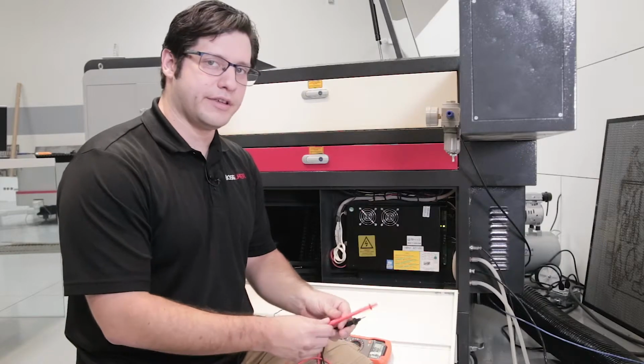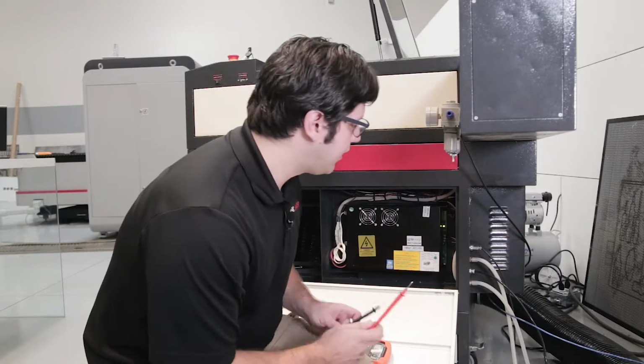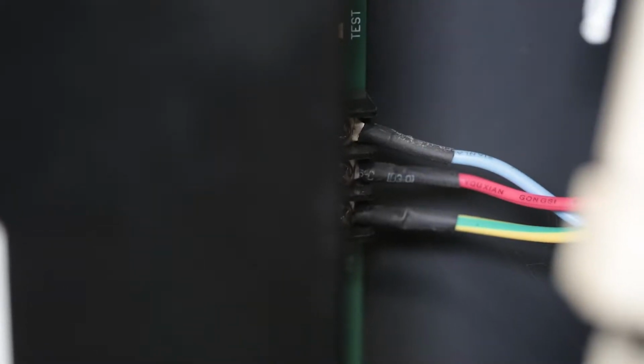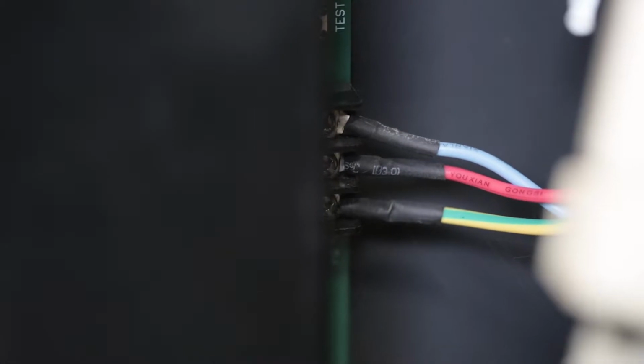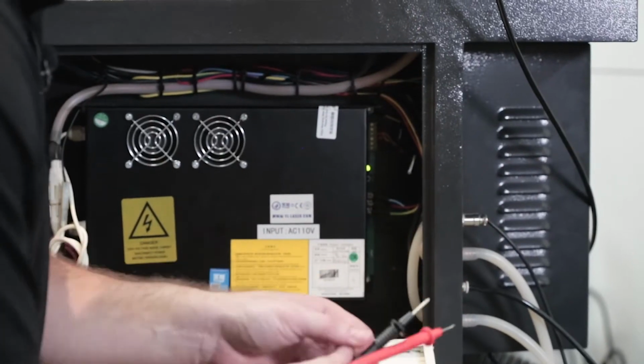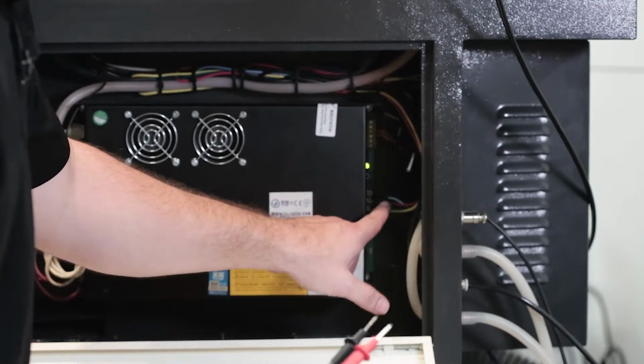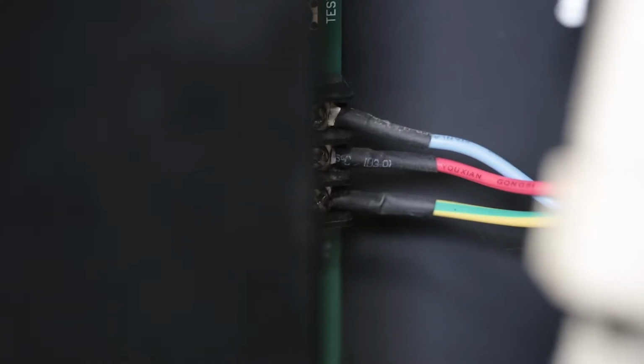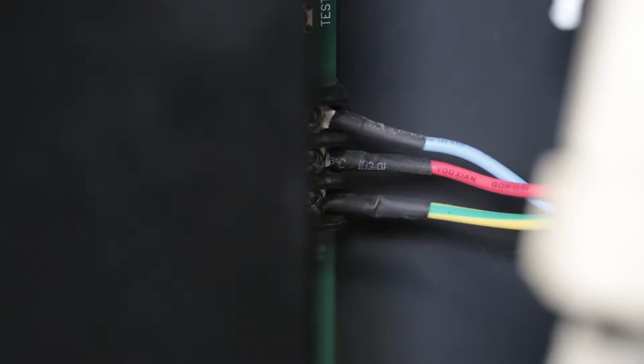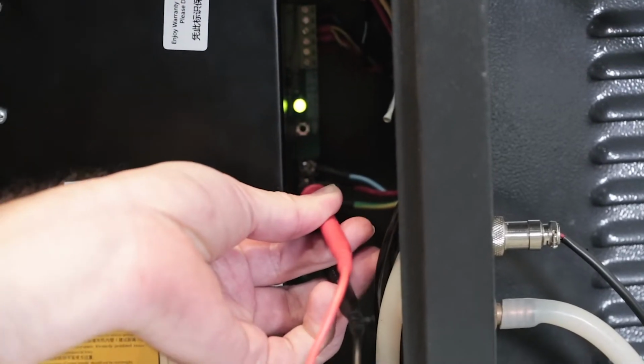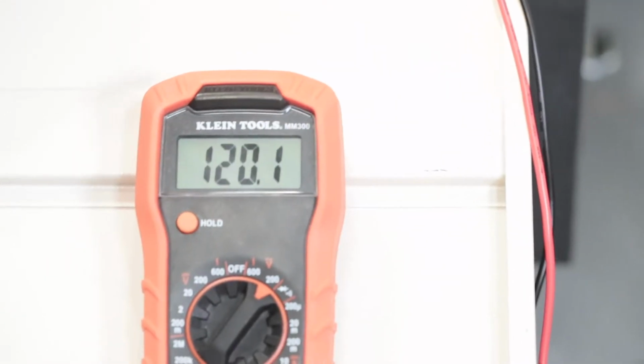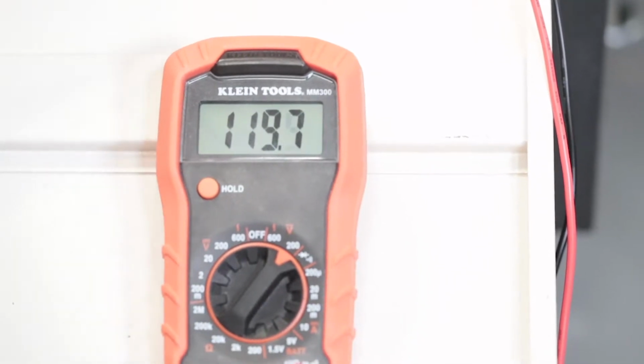Your red prong is going to go onto the red wire that's on the 3 wired connection here. That's where your power is coming in. So your red prong is going to go there, and your black is going to go on the ground, which is the green and yellow connection. So if you look, we are getting voltage to the power supply.